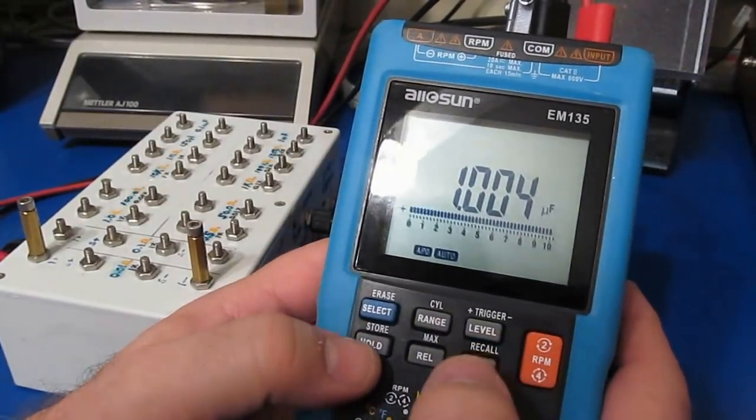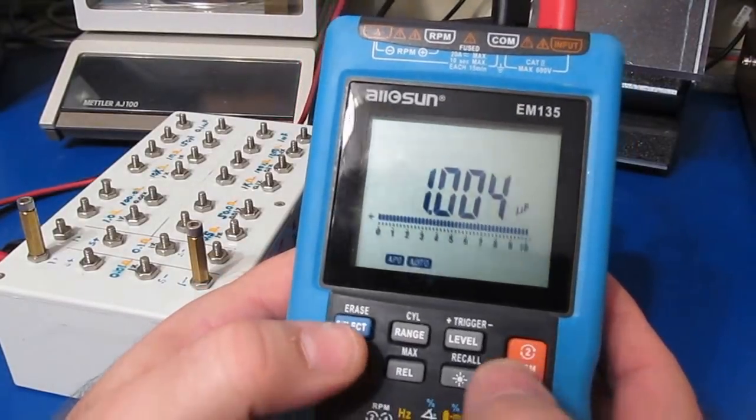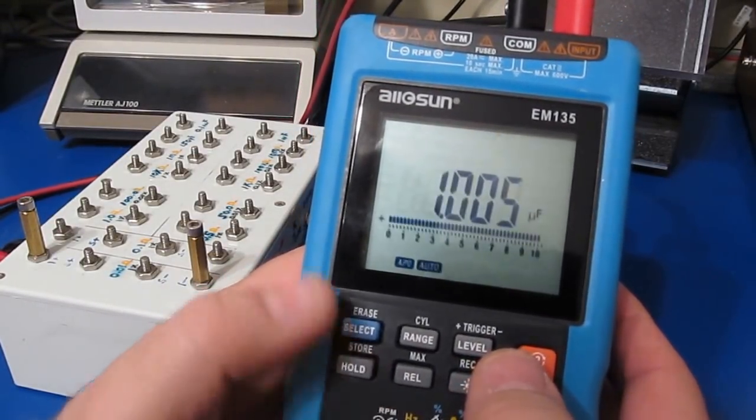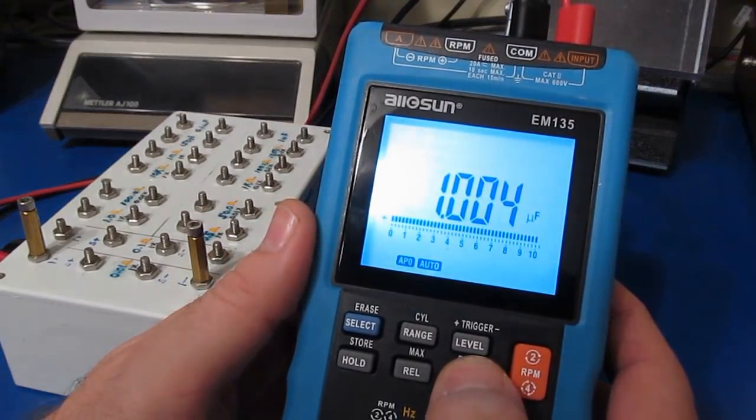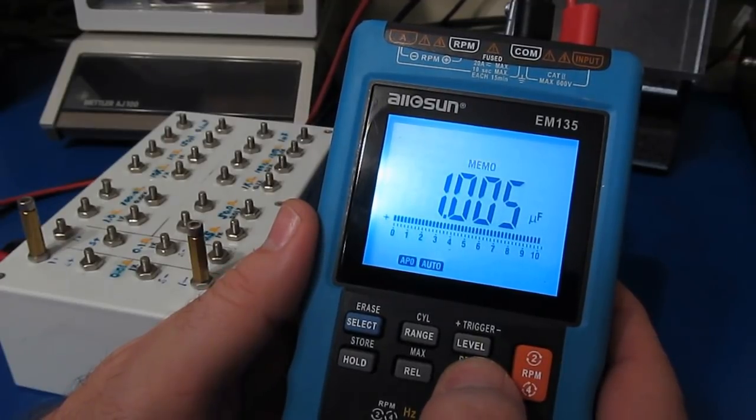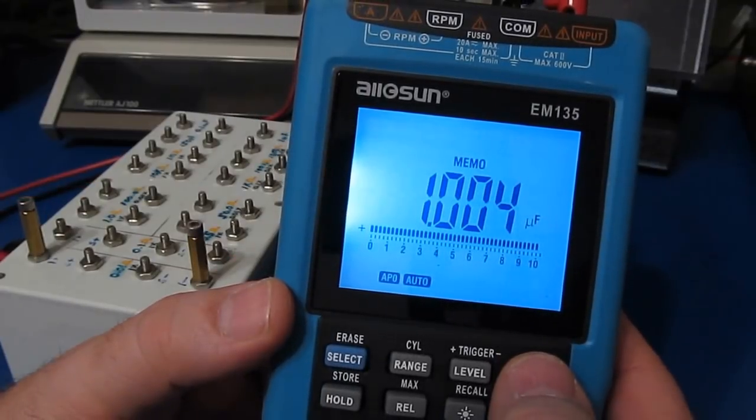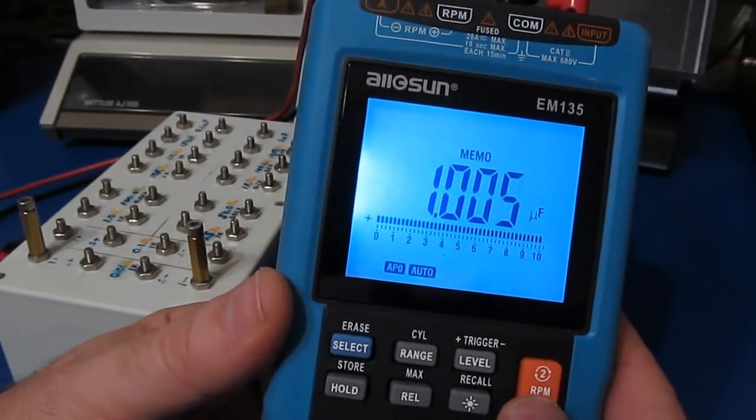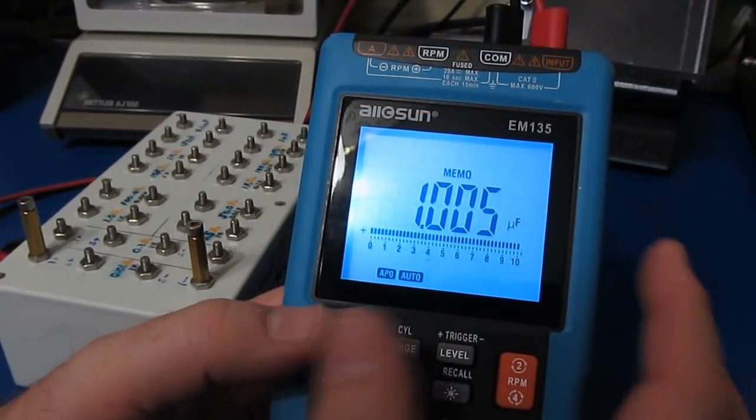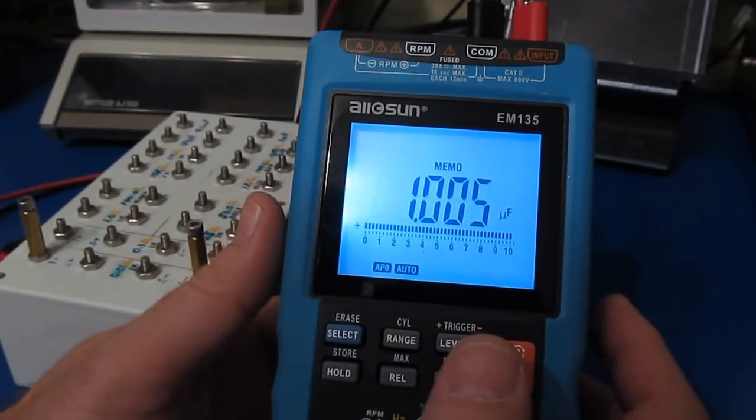The store feature allows saving measurements: selecting store saves to position two, then three. The recall function retrieves these: recall three, two, one. The display shows what mode it was in and the stored value. If taking many measurements and needing quick storage, this is a nice feature.